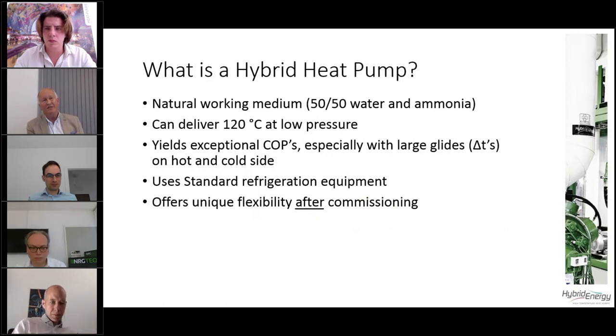What is a hybrid pump? In very brief, it's a natural working medium, 50-50% water and ammonia. Can deliver 120 degrees at low pressure. Then we talk about 25 bar. It yields exceptional COPs, especially with large glides, delta T's on hot and cold side, and it uses standard refrigeration equipment. And finally, but not at least, offers unique flexibility after commissioning. Just briefly a comment on that. We can change the mixture ratio between water and ammonia and correct the operation of the system when we see how the real temperatures will be. It's a considerable benefit comparing to pure ammonia systems that are more or less locked to design temperatures.